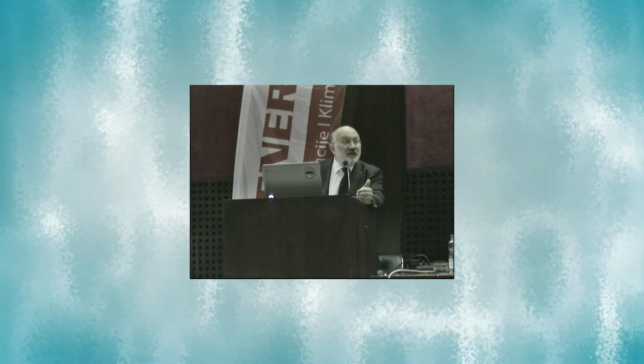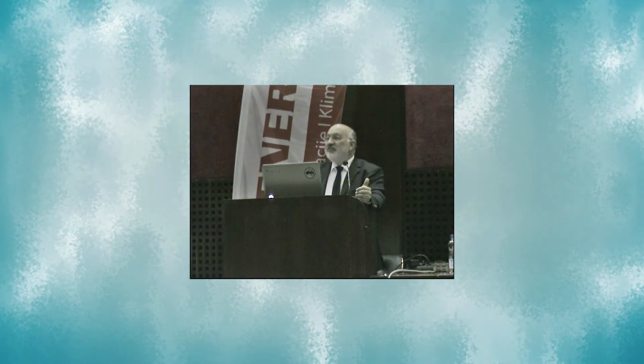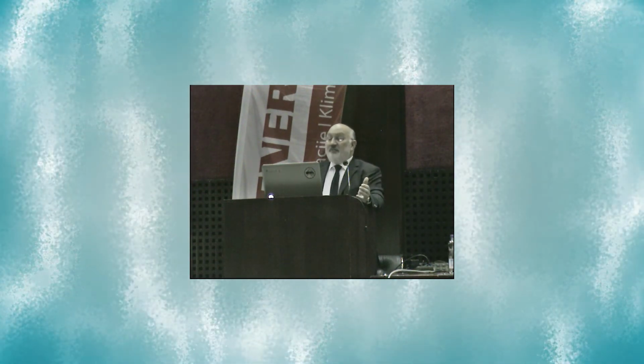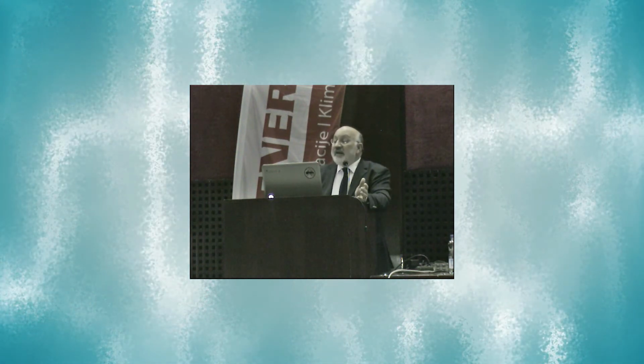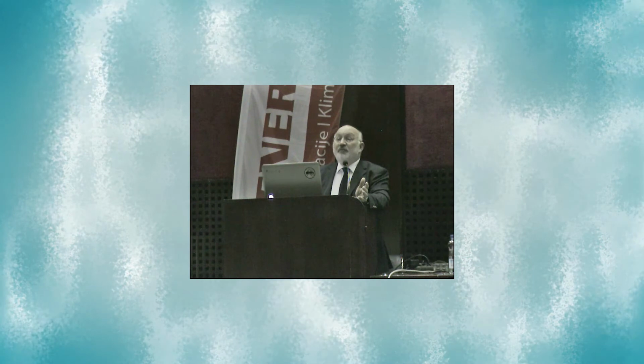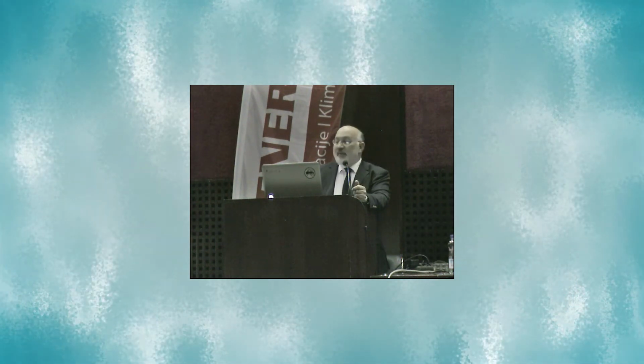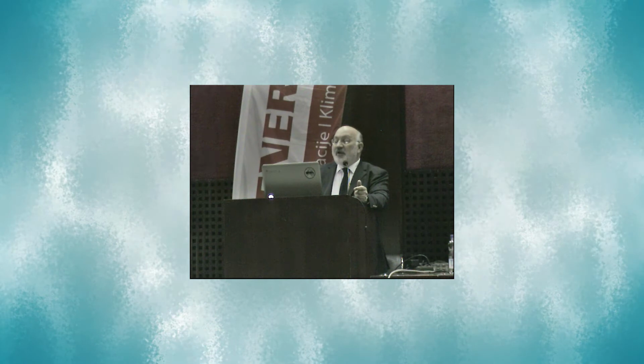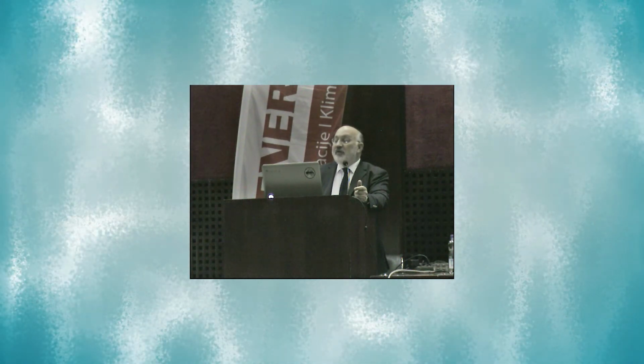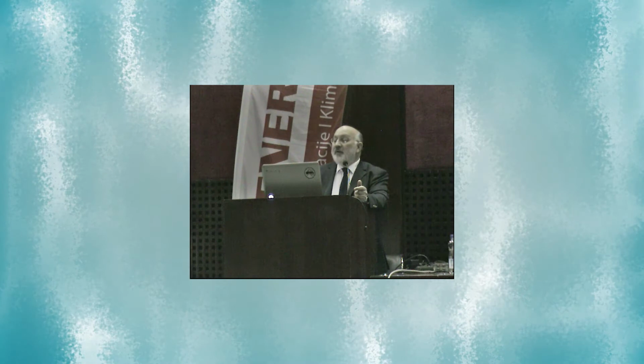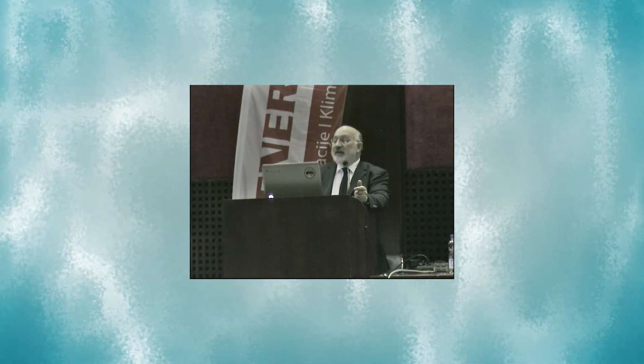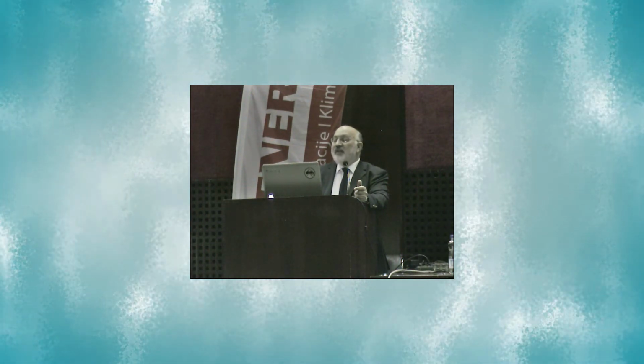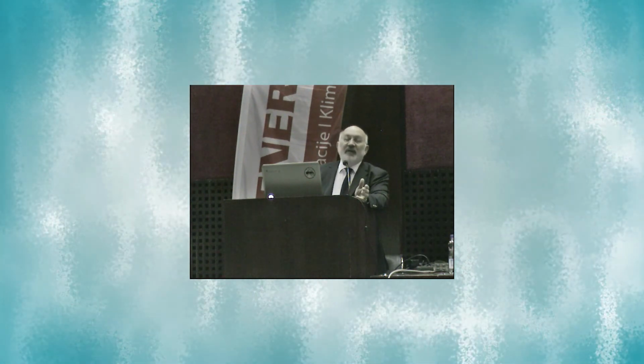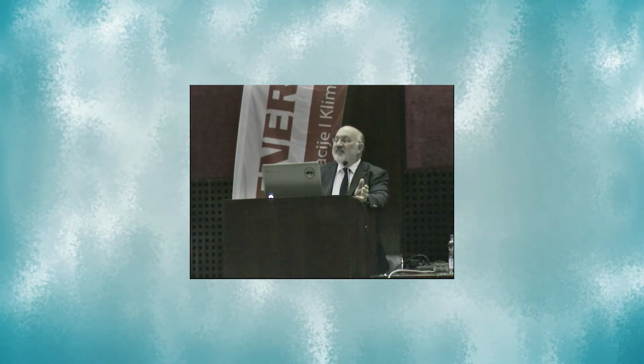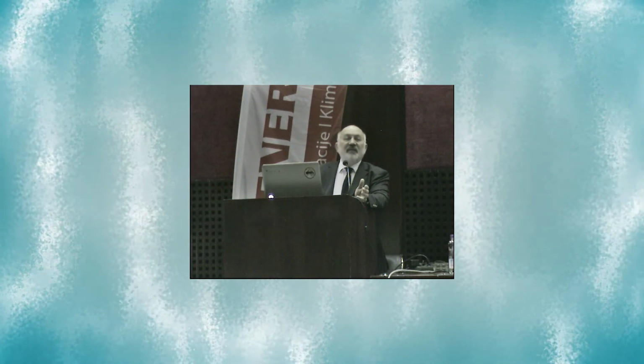But we have done experiments with CO2 in my labs at the university and at CTS, and developed several systems. On the right-hand side, this is a mini split with 3 kilowatt capacity. It shows R410A in blue and CO2 in purple, with capacity and COP at ARI conditions A, B, and C. You see slightly more capacity with CO2 and slightly less efficiency, basically a wash.